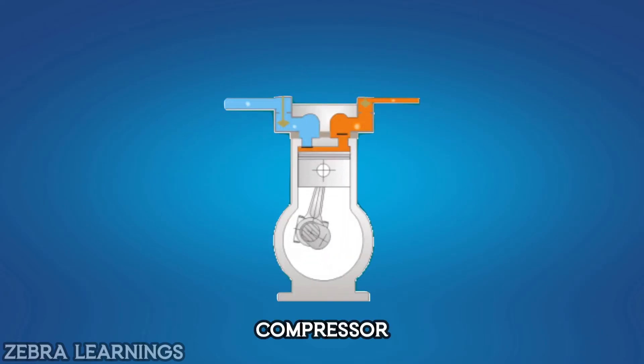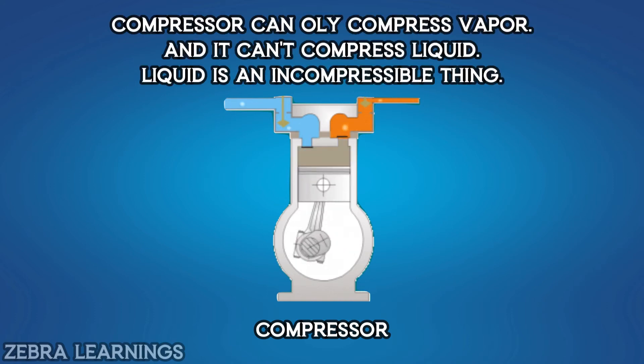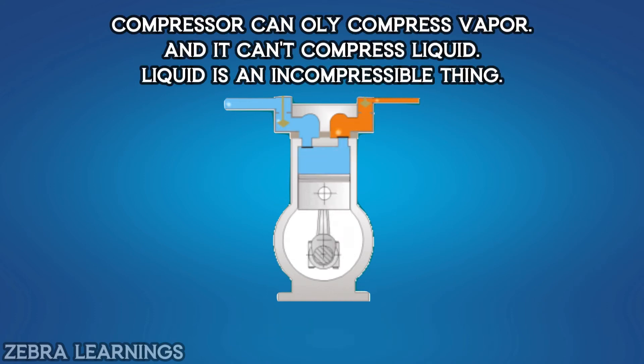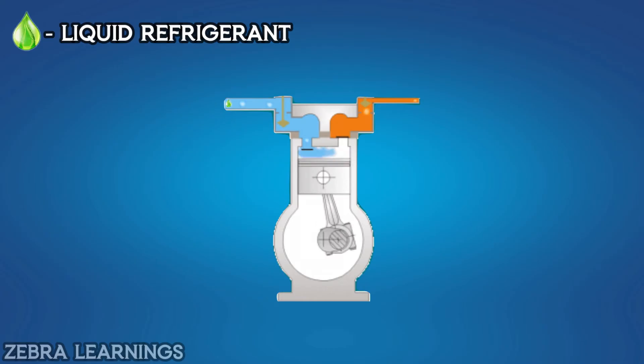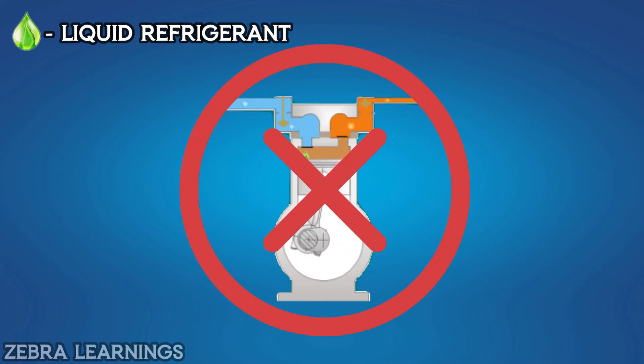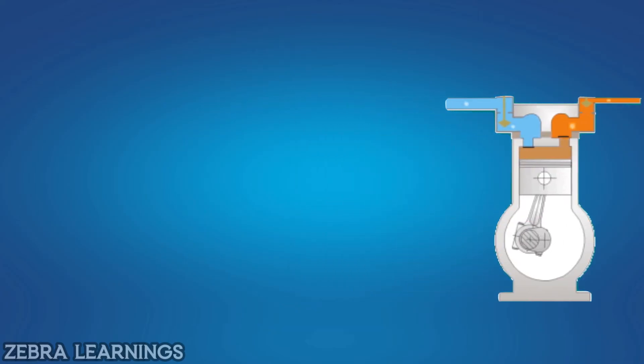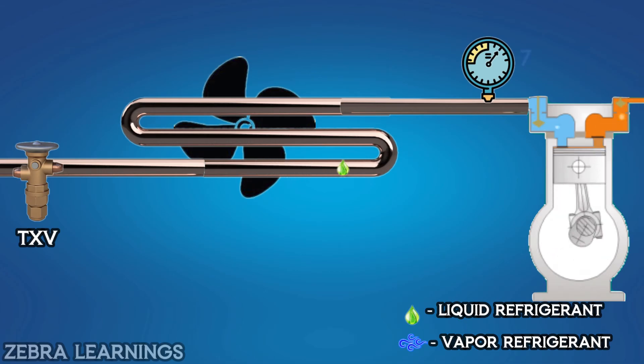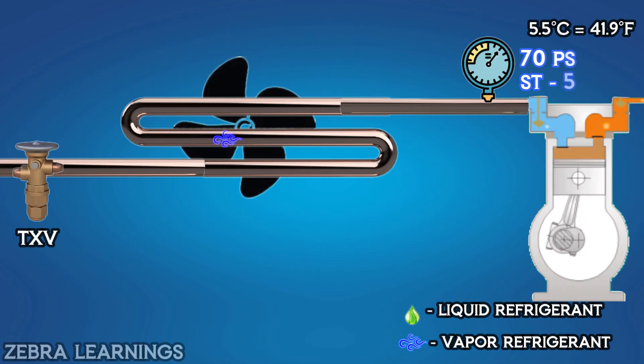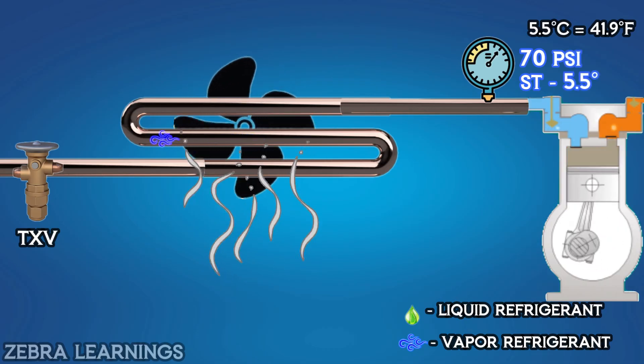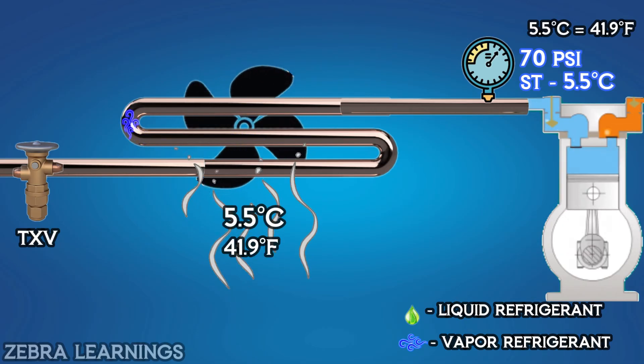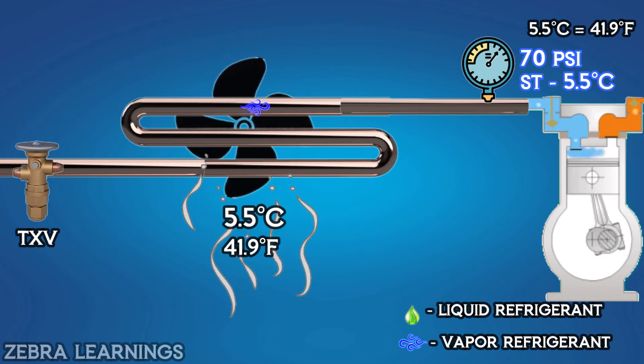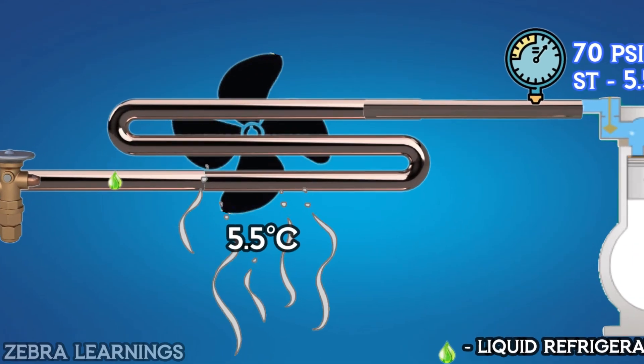As explained in our superheat and subcooling video, a compressor can only compress vapor and cannot compress liquid. If the refrigerant enters the compressor in liquid form, it will damage the compressor. If the R22 refrigerant inside the indoor unit is at a pressure of 70 PSI, its saturation temperature will be 5.5 degrees Celsius. So if we heat the indoor unit to 5.5 degrees Celsius, the R22 refrigerant starts boiling and turns into vapor.